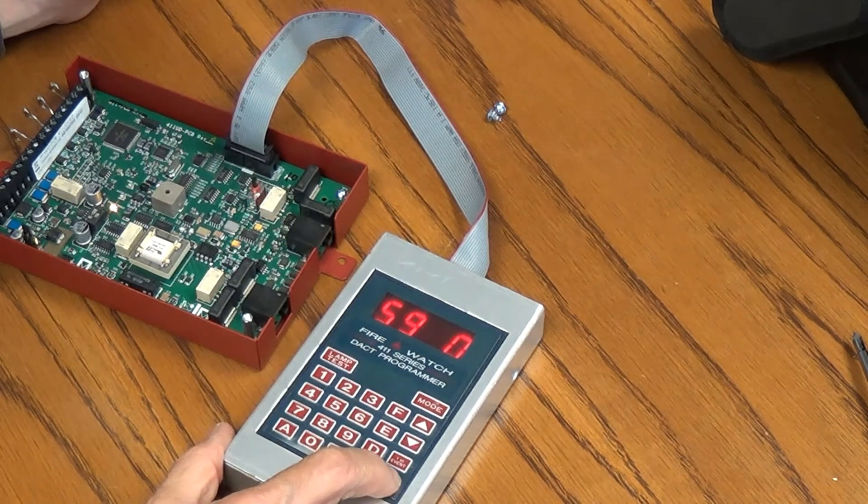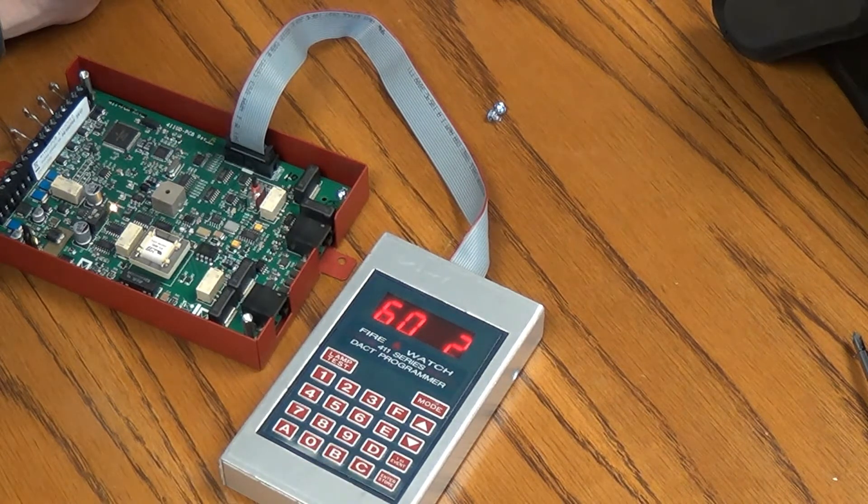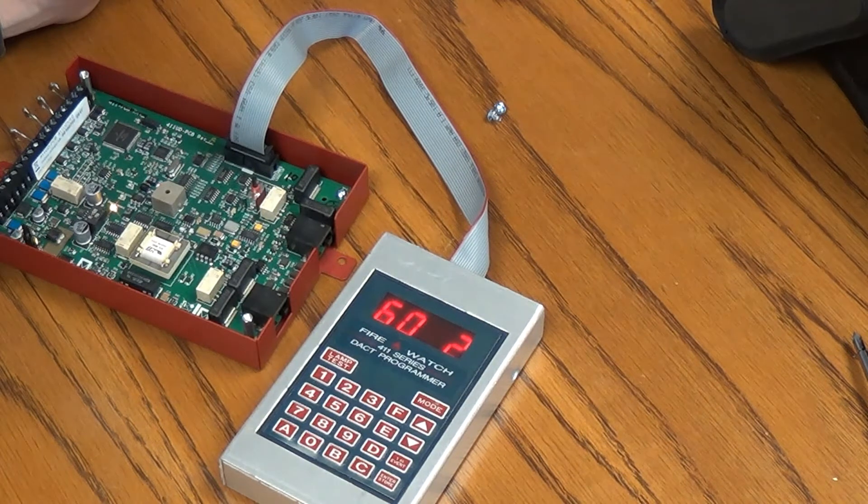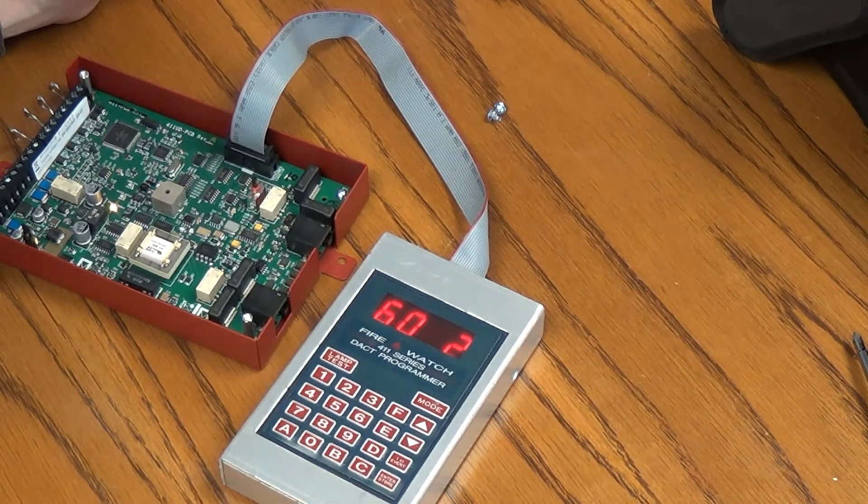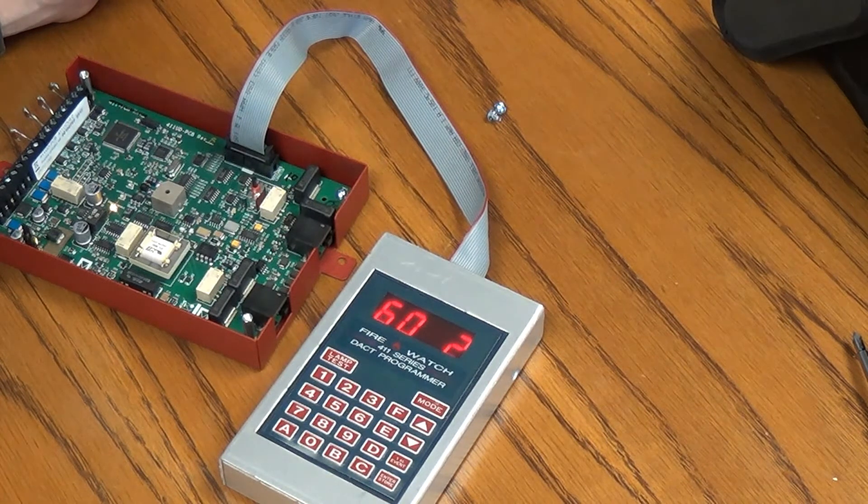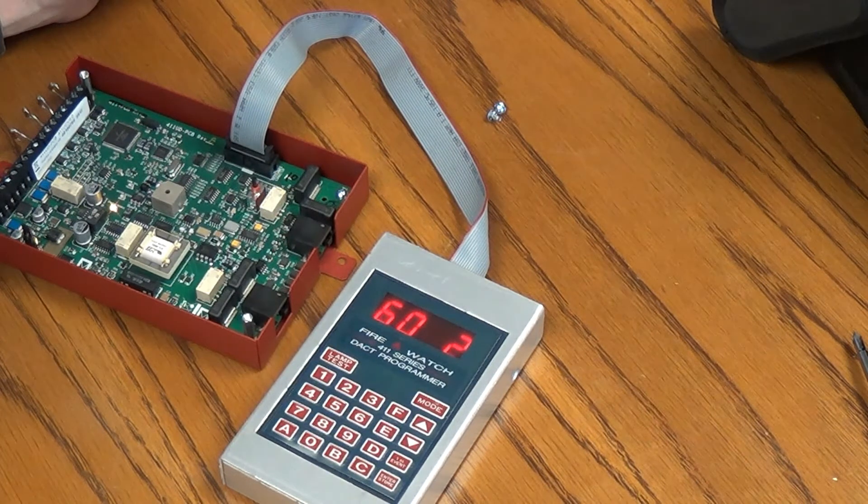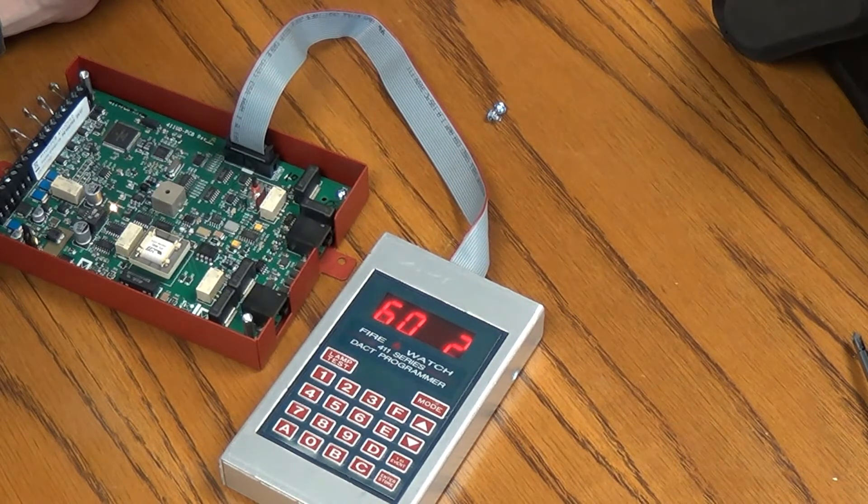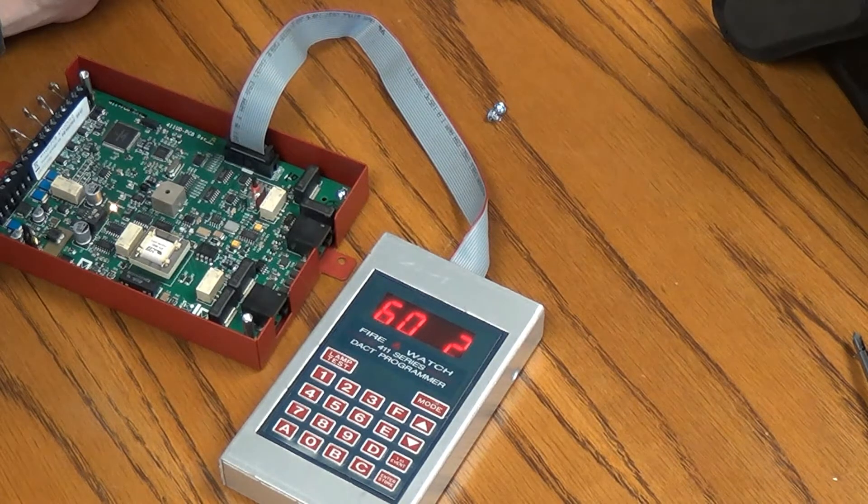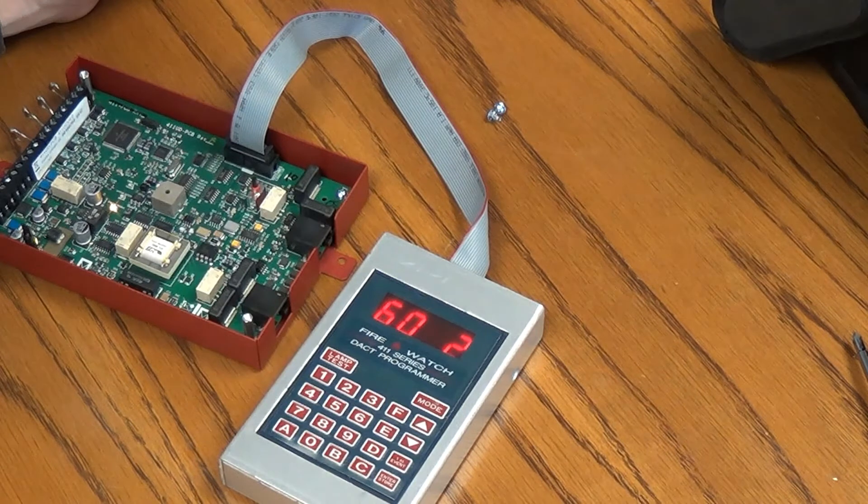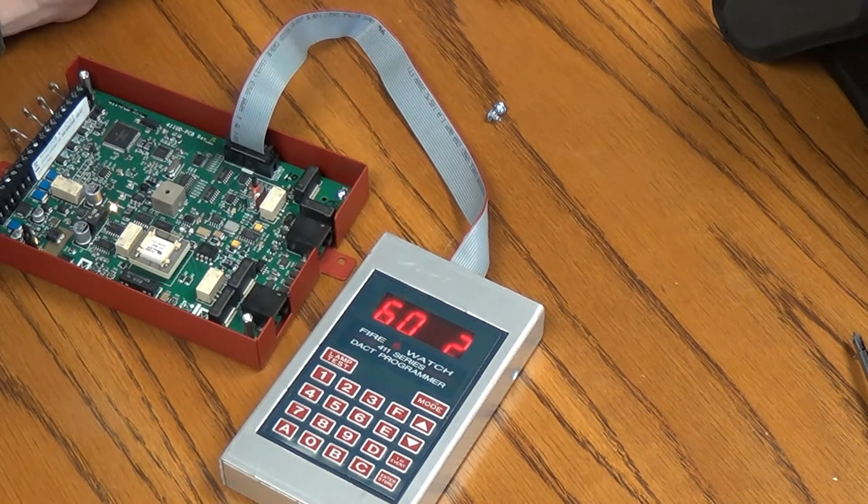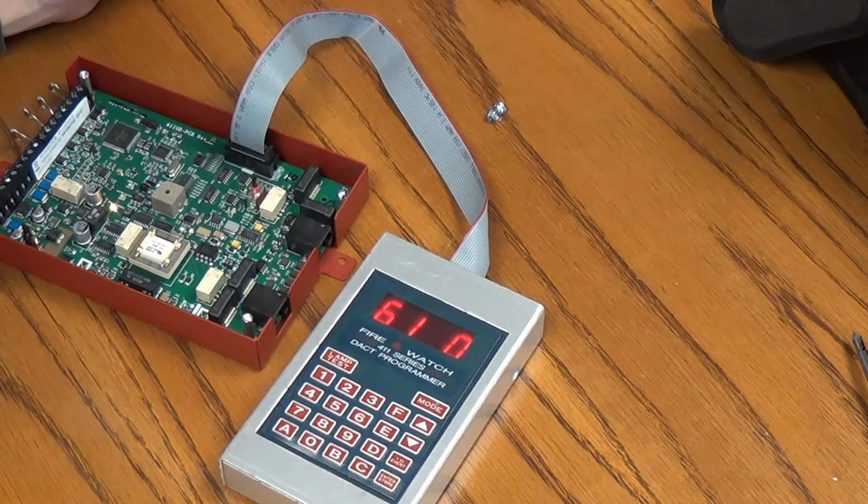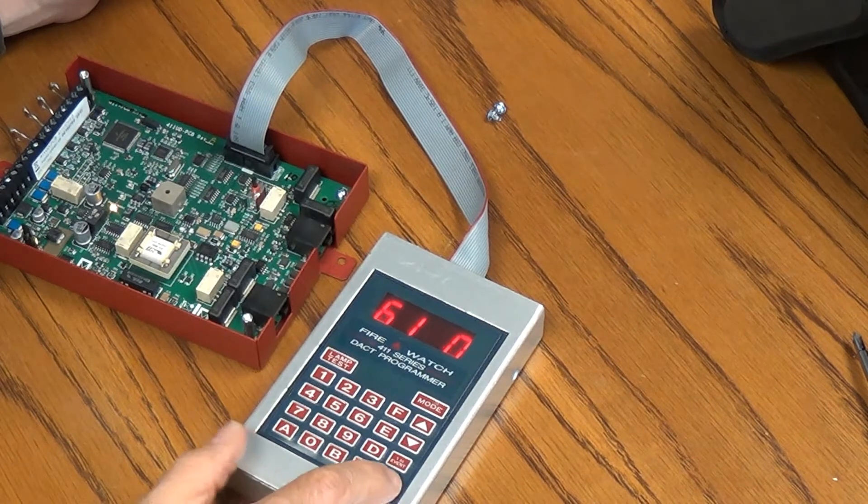The next one is 60, and 60 is power loss reporting delay. In other words, if it loses power, how long do we want it to wait before it sends a trouble signal? We have test intervals, either 0 for no delay, 1 for 1 hour, 2 for 2 hours, 3 for 6 hours, et cetera. Well we don't want any delay. If it loses power, we want to know about it. So we're going to enter a 0 here and press Enter. So we're at 61 now, which just remains as a 0.